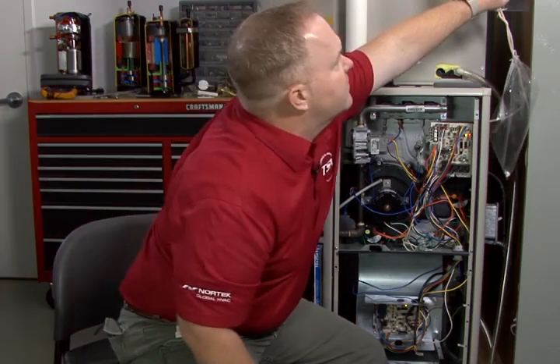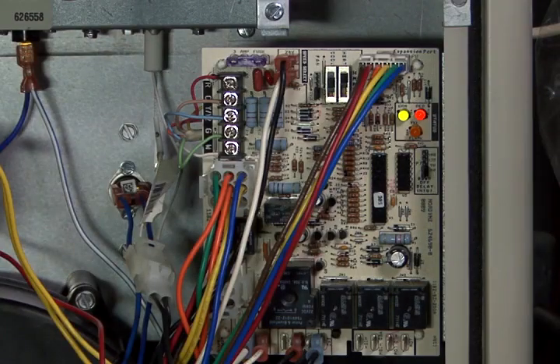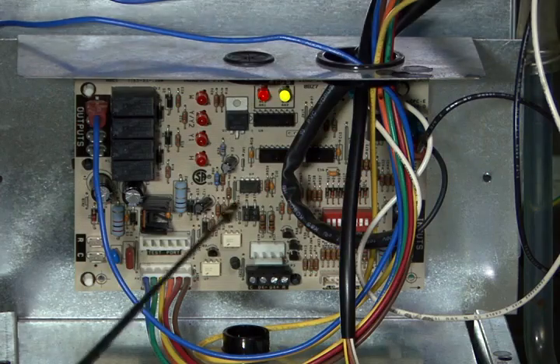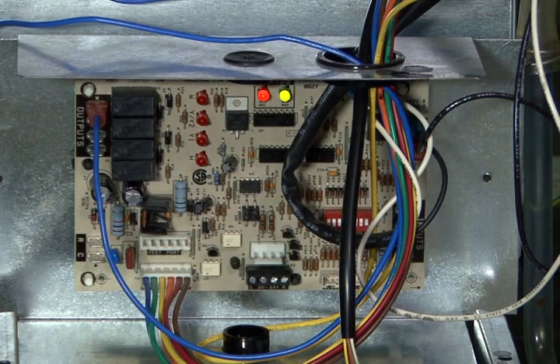So I'm going to go ahead and start this furnace up right now, and you're going to see that just as it's beginning the pre-purge sequence, the board's going to recognize that it's not communicating with the motor, and then it's going to go to a motor fault condition. Pre-purge is started. And right away, we're already seeing that the board is recognizing that it's not communicating properly with the blower, and it's producing the blower fault code.